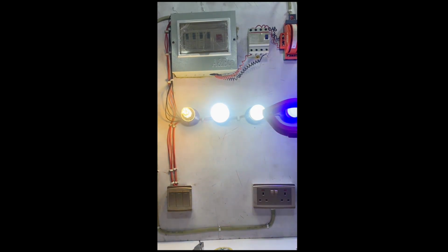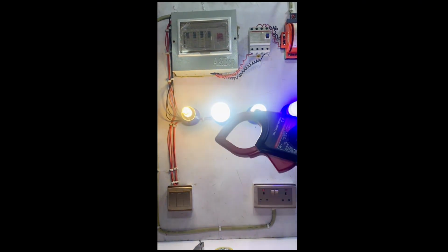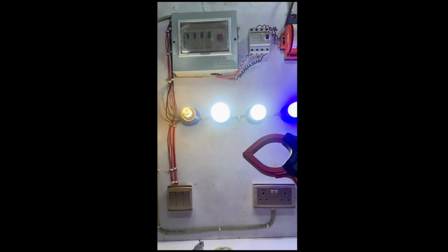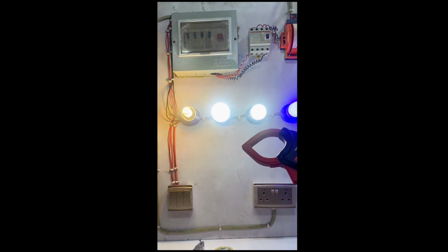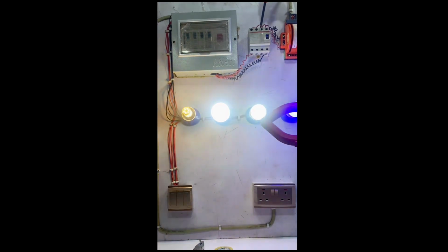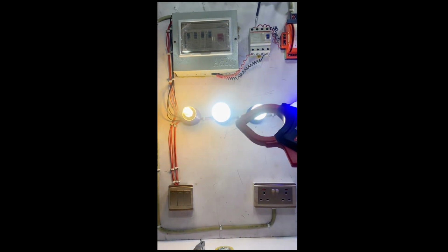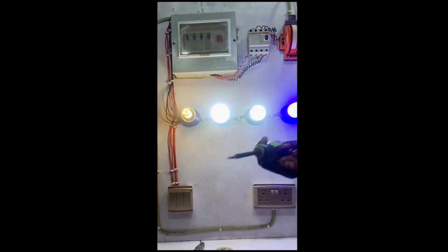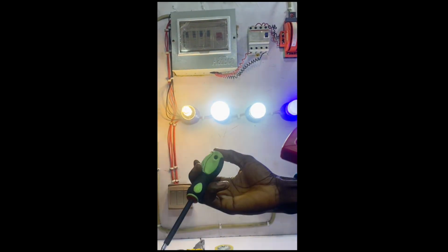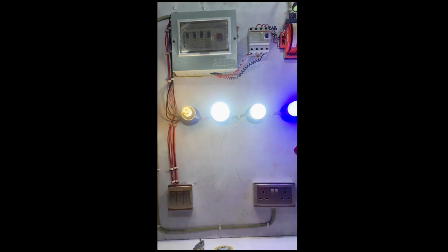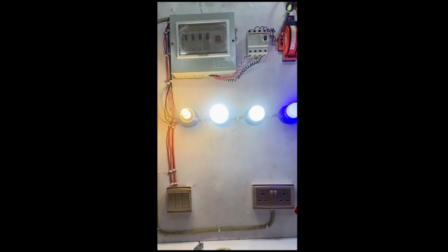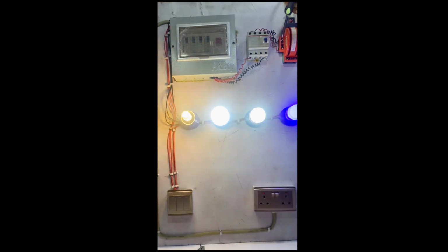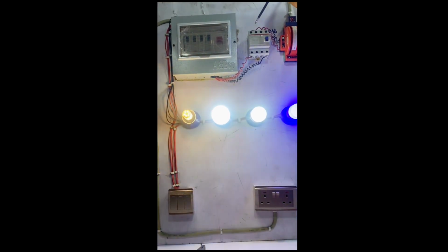Now, as you can see, this is the input to the changeover and this is the output of the changeover. So the output of the changeover enters the input of the residual current circuit breaker. So the upside is the input of the residual current circuit breaker. You can even test to know the direction in which the current flows. So we are going to use our tester. This is my tester. Here is the direction of current flow. It flows from here down here.